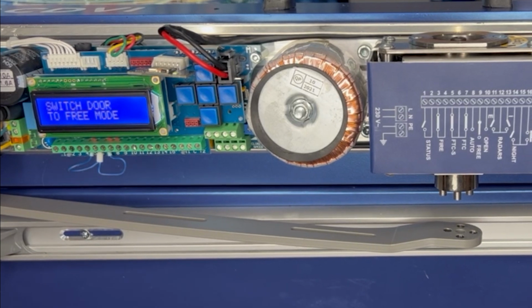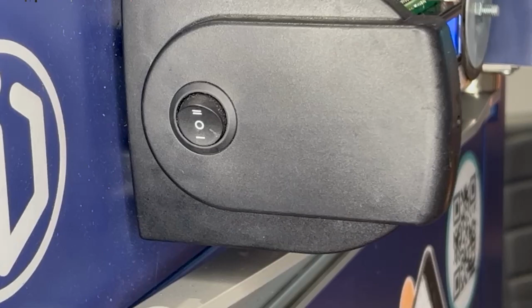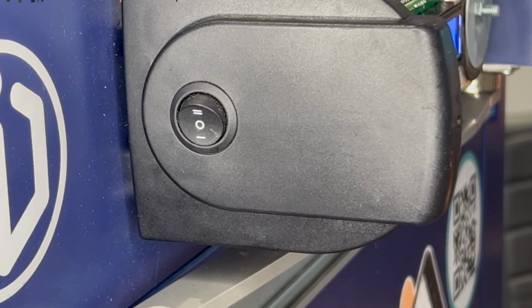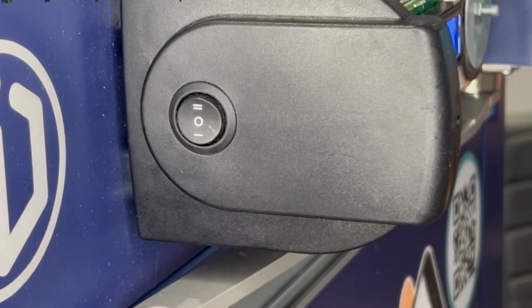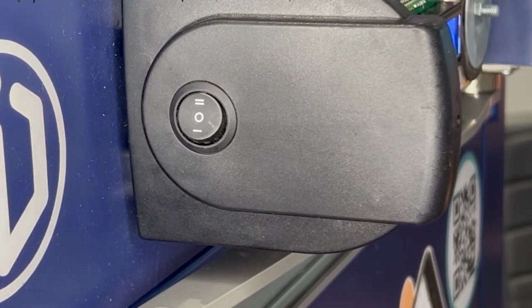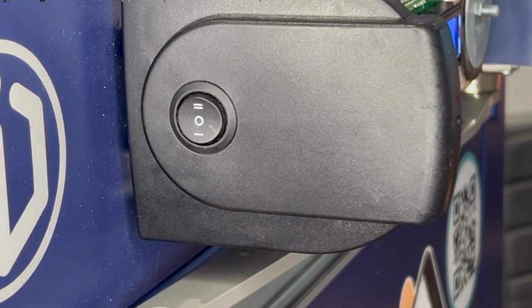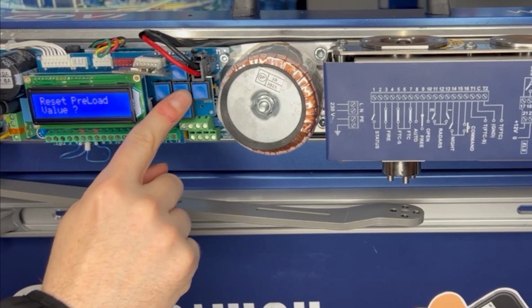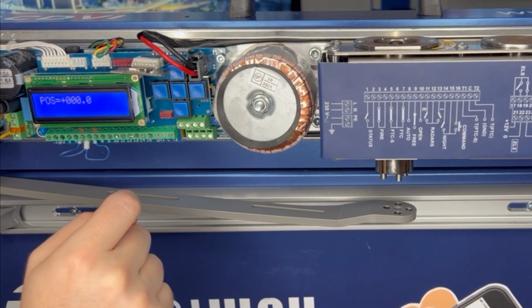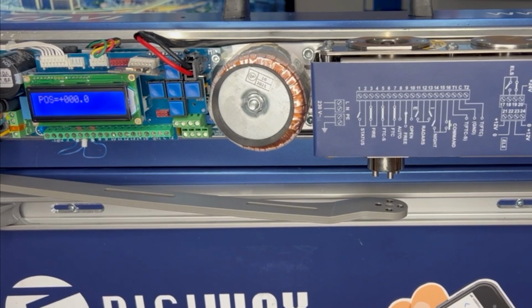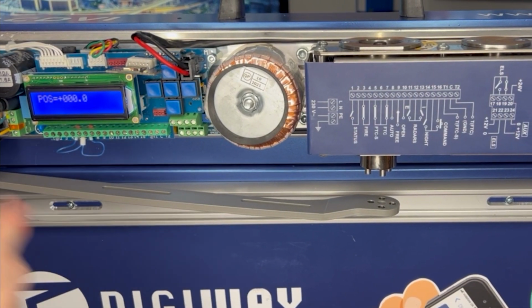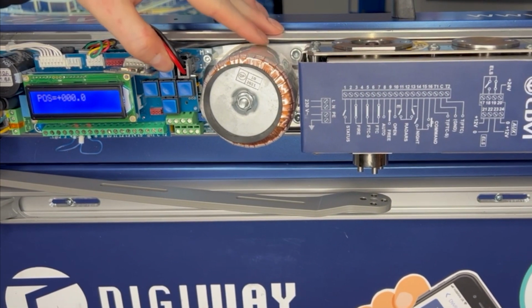As it says there now, it says switch door to free mode. On the side here, we've got a rocker switch, which is in number 1, which is our auto mode. We have the center one, which is turned off, which is in free mode. And then we have the top one, which is in a remain open. So it says there, reset preload value. I'm going to click OK. And now what we need to do is set this to anything above 90, and we use the up button to do this.